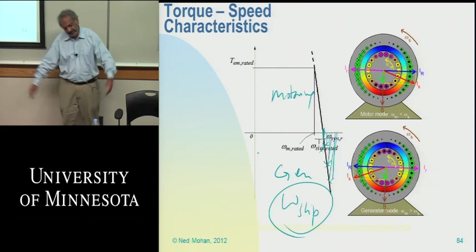So very seamlessly, these machines can, as this torque speed characteristic would show you, be done in a second here, okay? If you will bear with me. This is the motoring mode, and this is the generator mode over here. And this is where the rotor is rotating at synchronous speed, but at a speed higher than the synchronous speed, if this rotor is turning, then you go into the generator mode here, okay? So you can go seamlessly from the motoring mode to the generator mode. We are, of course, interested in the generator mode. By controlling the slip speed, you can control whether you're at this point, at this point, at this point over here, right, in terms of torque. You have different speeds at which the rotor is rotating, and therefore you have different slip speeds, and therefore different torques that are produced. So that's your torque speed characteristic.